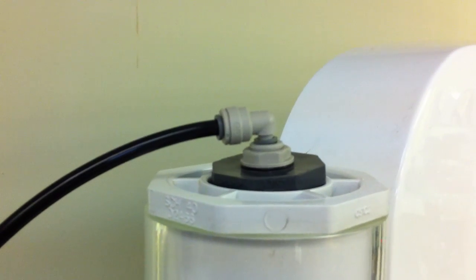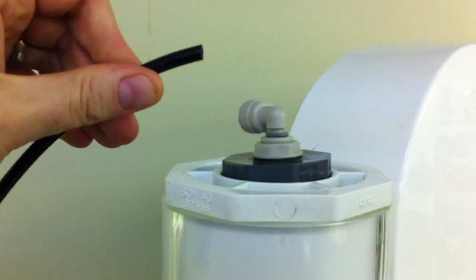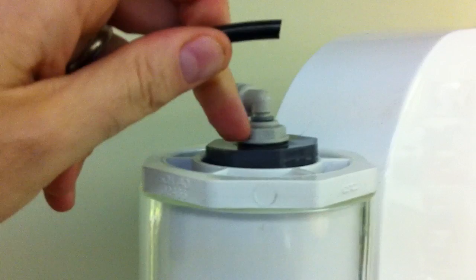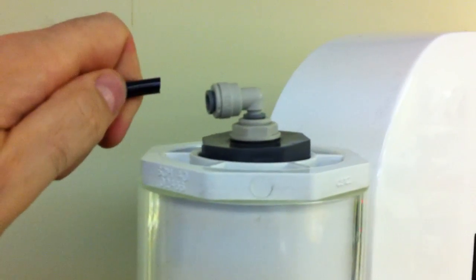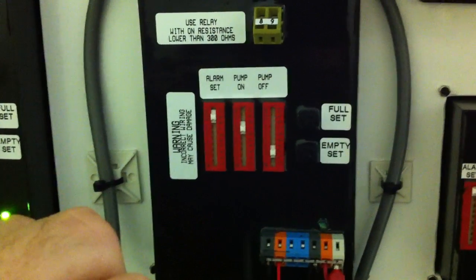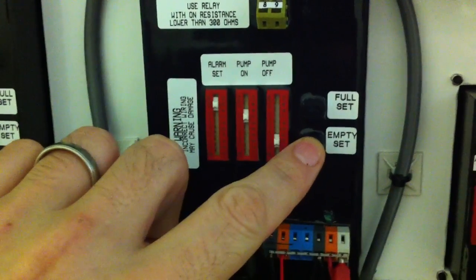To calibrate for empty, we can simply unplug the tubing to simulate empty, either from the top of the tank fitting or the tank sender, the SIM. Once empty is simulated, we come to the back of the panel and press the empty set button.